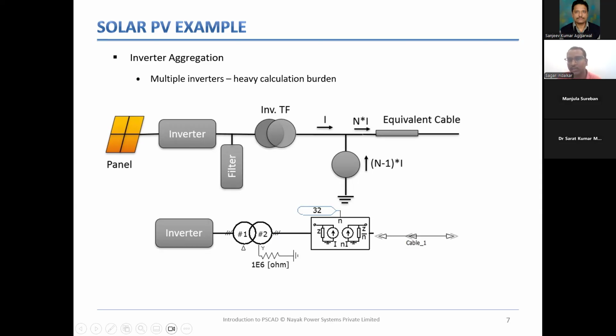instead of modeling hundreds of inverters, I will model one inverter with one inverter controller, and then I will use something called a scaling component. So this box which you see is a current scaling component, and depending on the number of converters, I will put this input as, let's say there are 32 converters. I will put 32 as an input to this, and it will multiply the power output of each inverter 32 times. So this component is readily available within the PSCAD library. It's called the current scaling component. And again, the cable. Now, since the inverters are clubbed and aggregated, cable is also aggregated into an equivalent cable.